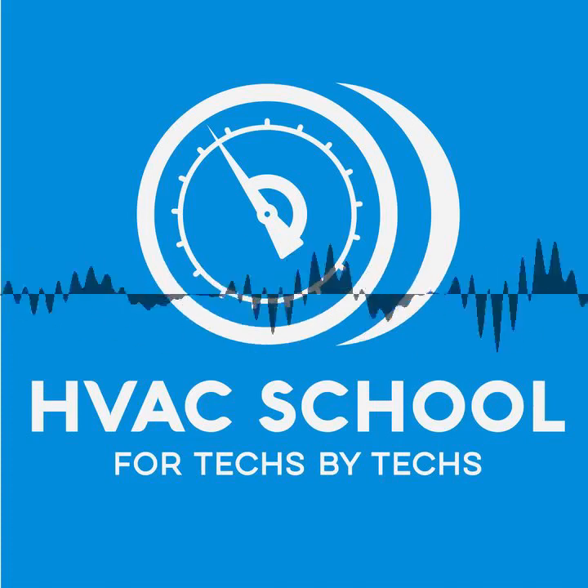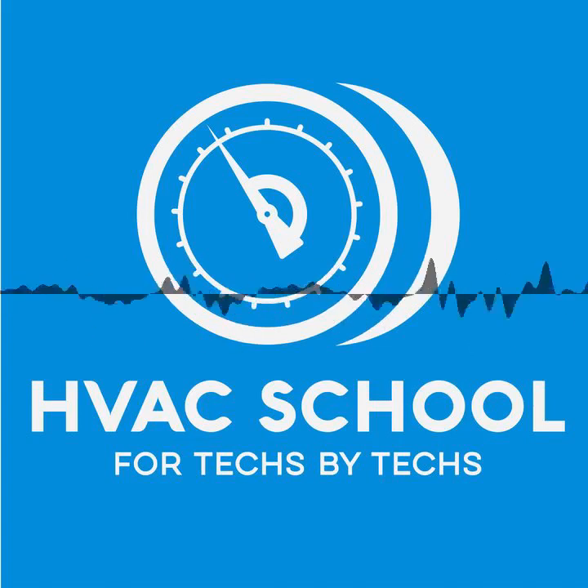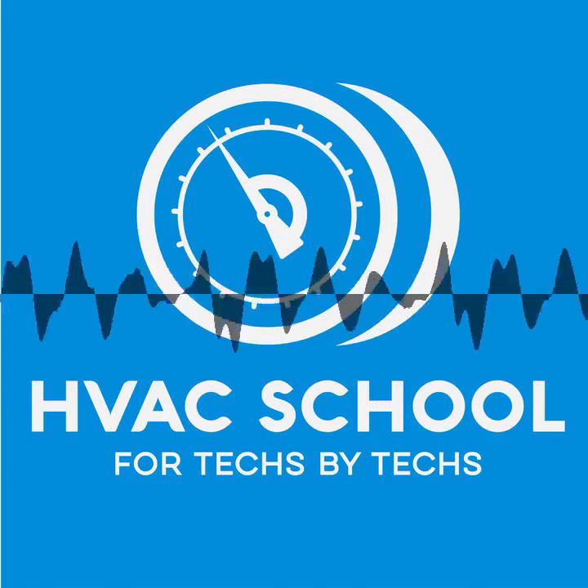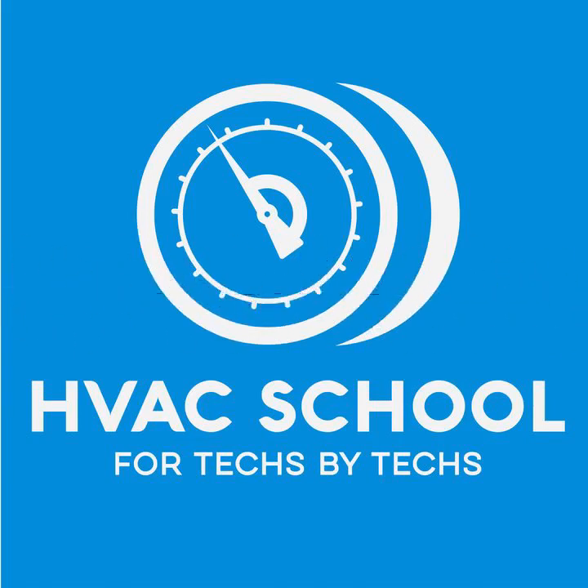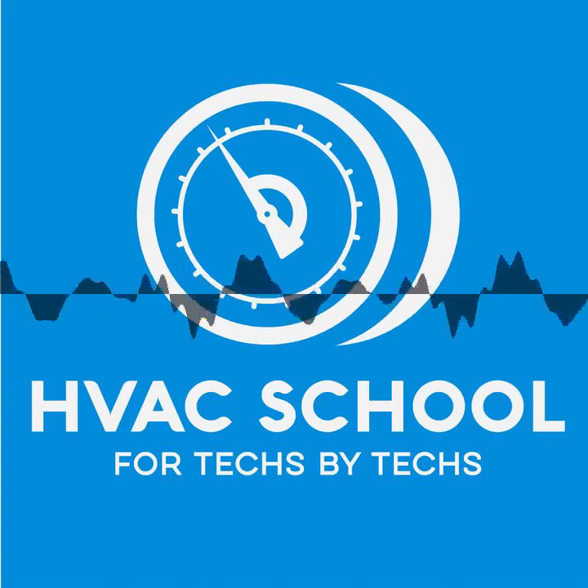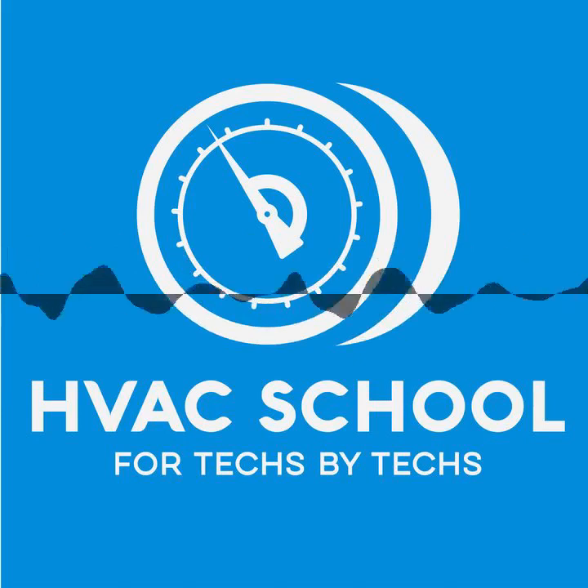Right. The part you said about the low charge, here's the funny part. Let's just say I had 3 or 4 units connected together, like cassettes or fan coils or wall units. When I'm running low on charge, the system will use the temperature outside and it will rev the compressor up, trying to look for my ideal suction. Mm-hmm. And maybe some of the units, if it's a fan coil that's long, you'll feel half of it cold, like an expansion valve that doesn't fill up. Right. You'll have half of it cold, and you'll have half of it hot, like if it was in heat mode. The reversing valve will slip a little bit, go into heat mode to get that suction up, and then it'll close back again to go up and down. So it's pretty inconvenient. So you have to be familiar with some things that some people look at and say, why? Those are things that I learned from working on them. Cool.